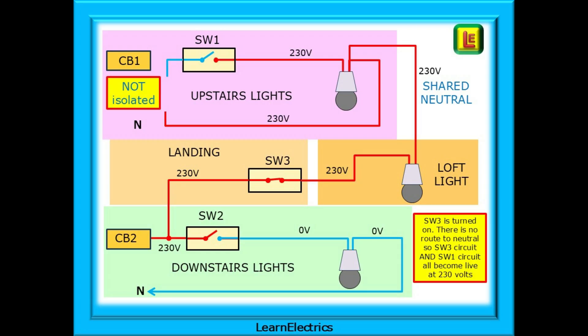Look at what happens to the lighting conductors when SW3 is switched on, put into the closed position. SW3 is turned on. There's no route to neutral, so SW3 circuit and SW1 circuit all become live at 230 volts. It's the shared neutral that carries the 230 volts into your once isolated upstairs lighting circuit.